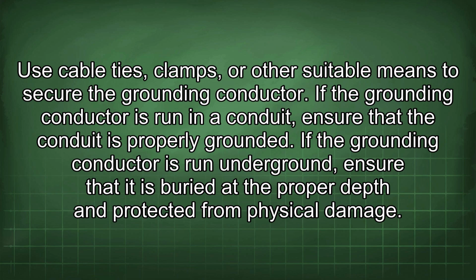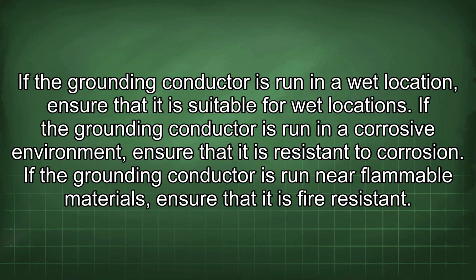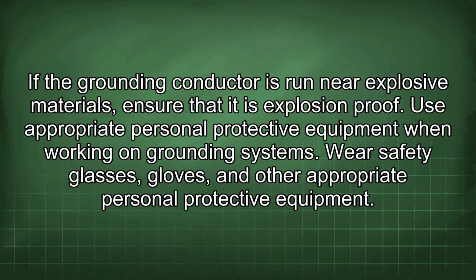If the grounding conductor is run in a conduit, ensure that the conduit is properly grounded. If the grounding conductor is run underground, ensure that it is buried at the proper depth and protected from physical damage. If the grounding conductor is run in a wet location, ensure that it is suitable for wet locations. If it is run in a corrosive environment, ensure that it is resistant to corrosion. If it is run near flammable materials, ensure that it is fire resistant. If it is run near explosive materials, ensure that it is explosion proof.